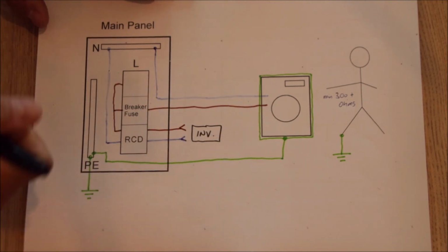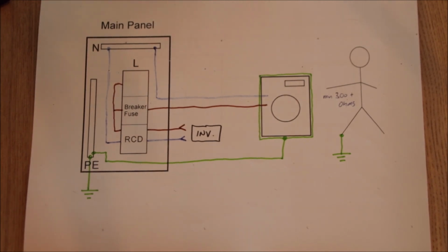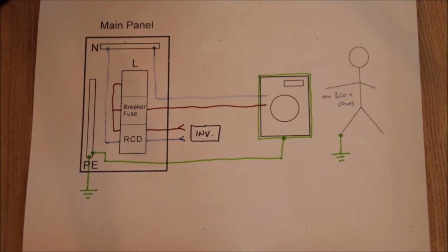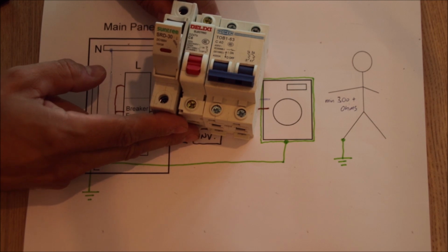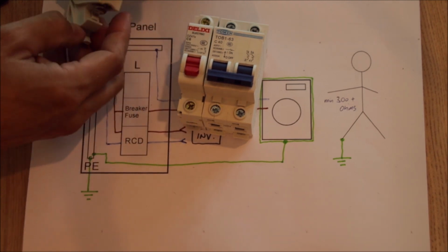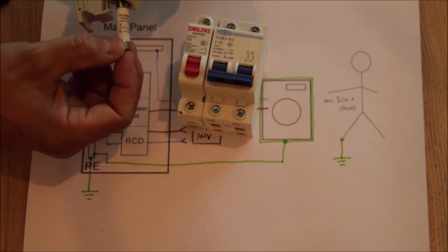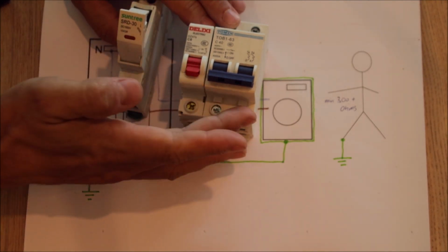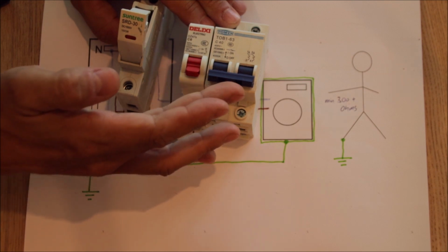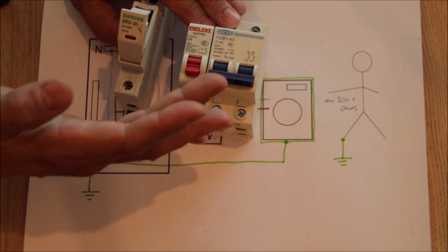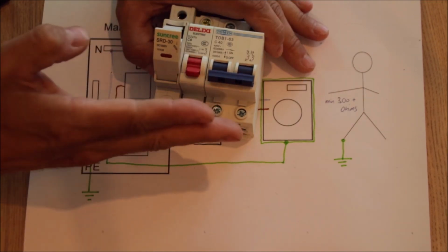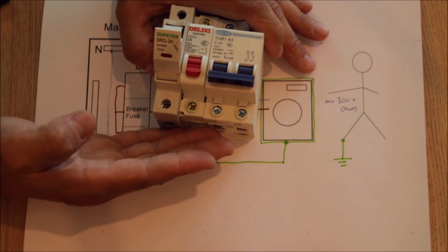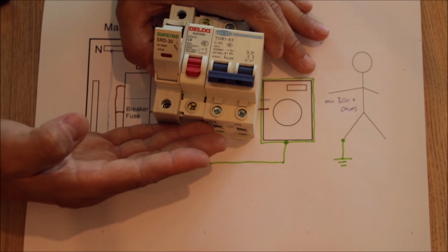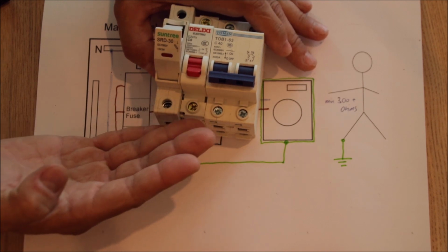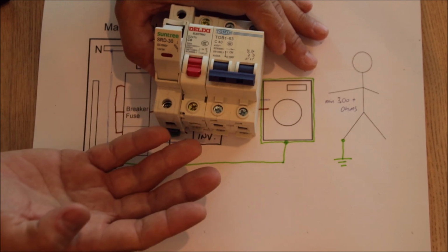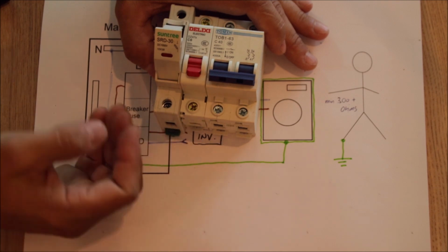We have protective devices. When we're talking about protective devices, there's two groups. We have first breakers or fuses. So this here is a fuse. Then breakers, one pole where you only switch your L, the hot wire, and then double breakers where you switch the hot and the neutral wire. Breakers actually do not belong to the earthing protection. Breakers belong to device protection and the protection of wiring. The main purpose is, in case of short circuits, to open a circuit so that there is no fire risk because of the high currents flowing.